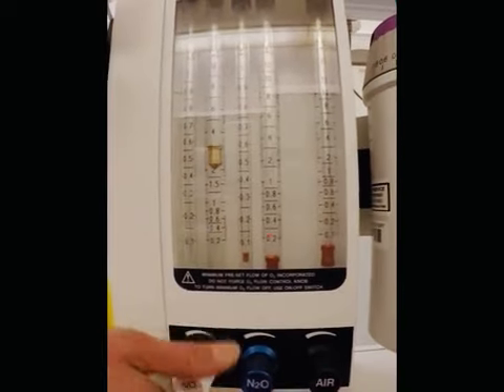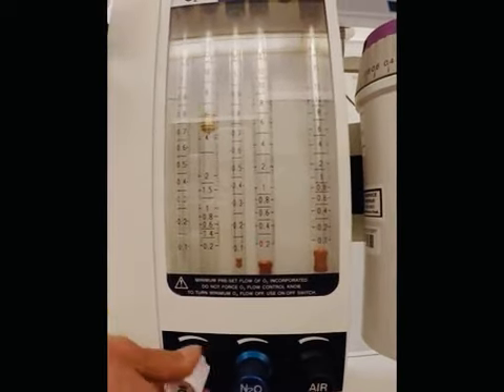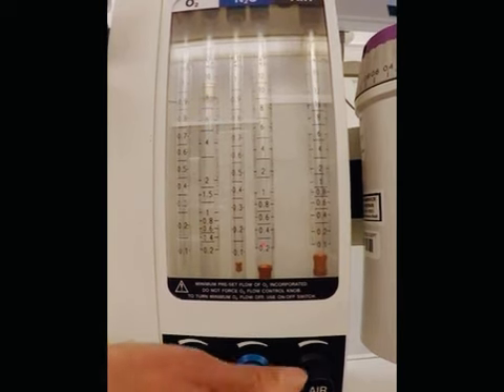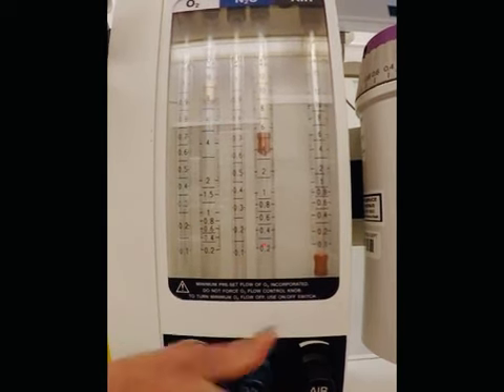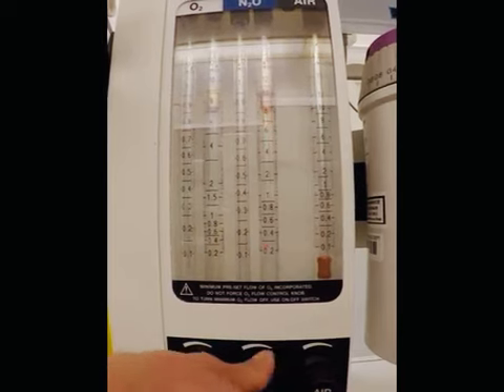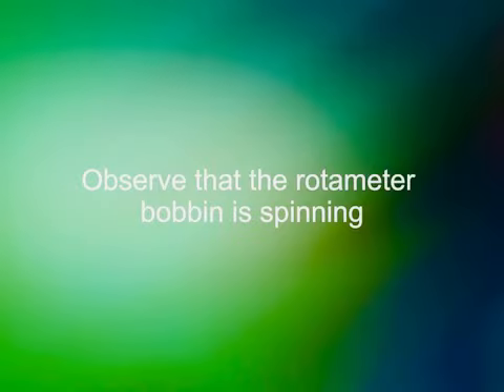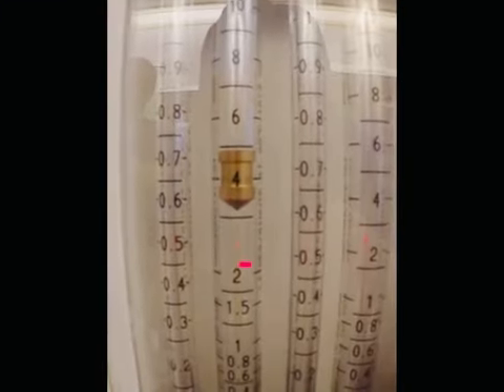Turn both the oxygen and nitrous oxide on fully throughout their ranges, checking that each bobbin is spinning and not sticking within the tube. Do the same for air if being used.